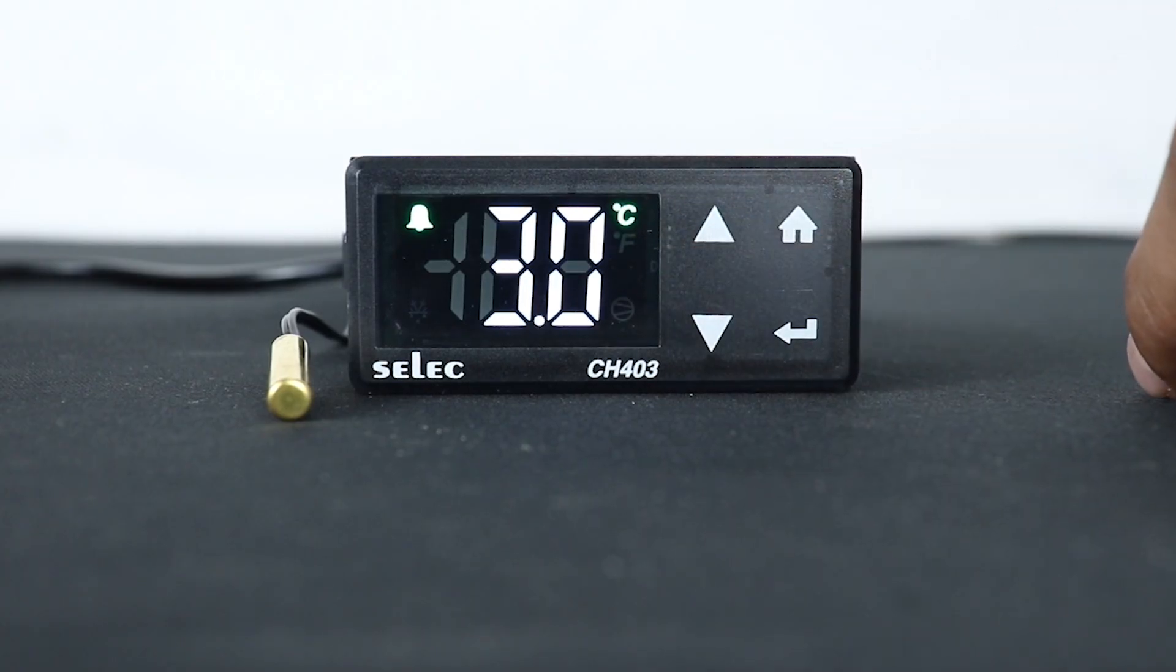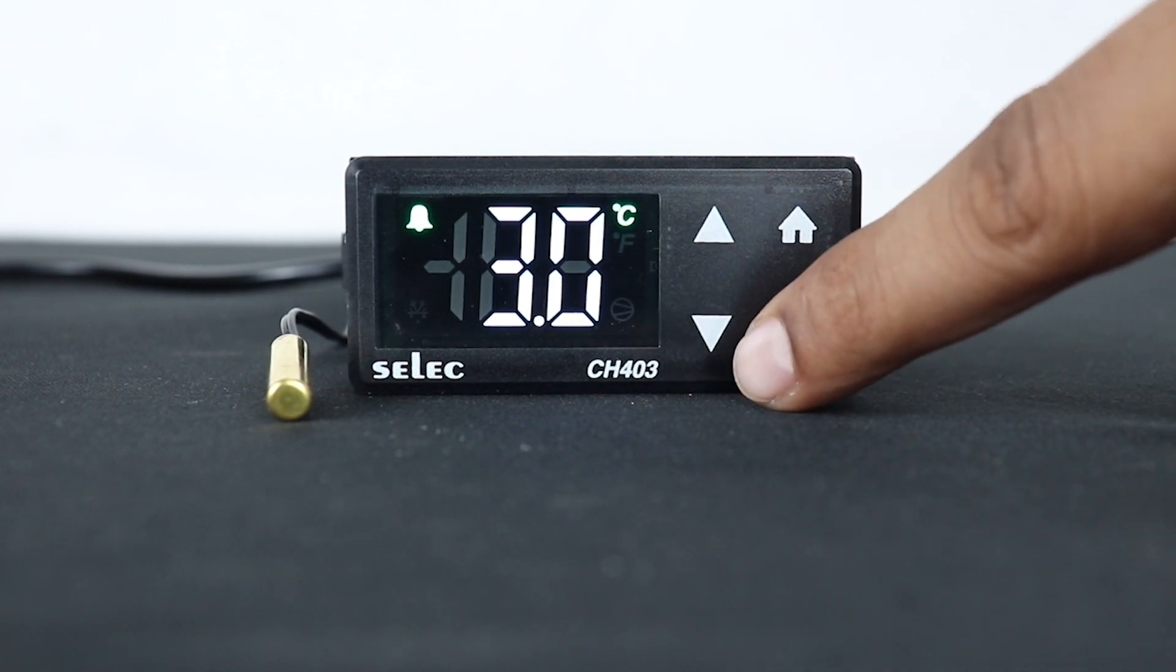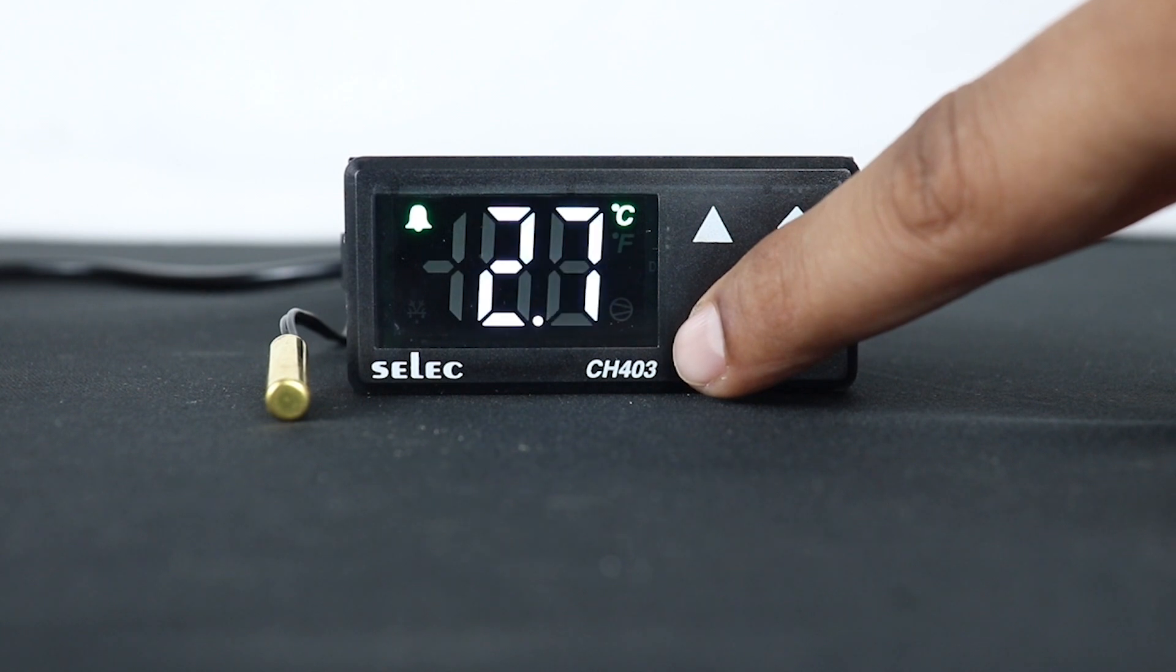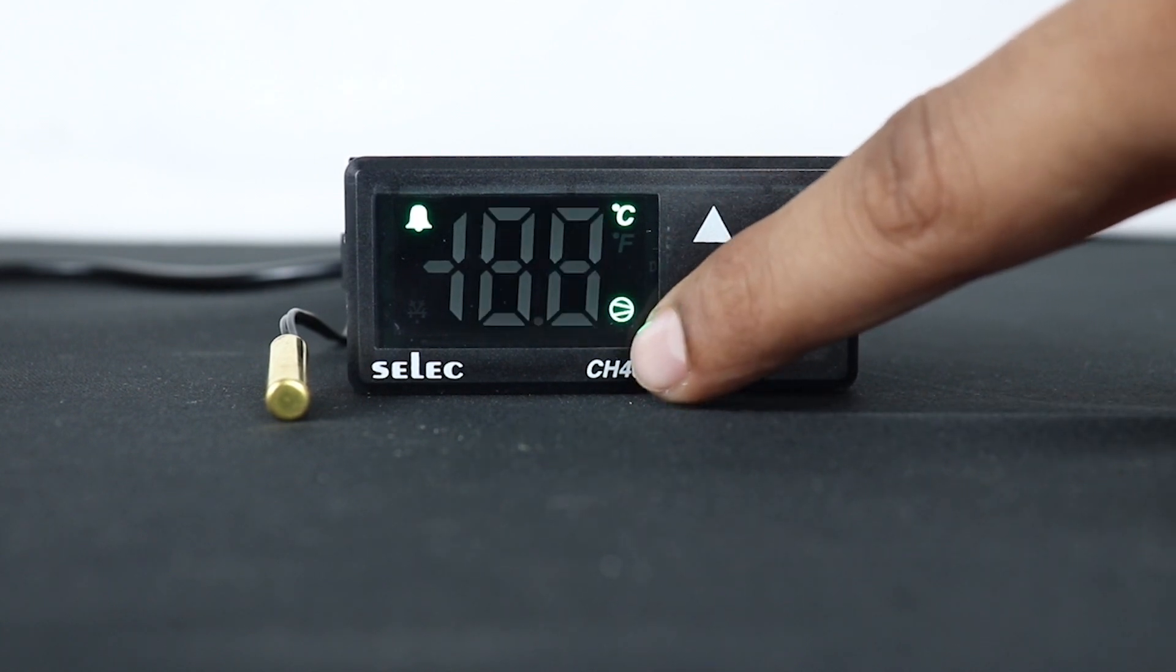P6 denotes restart time delay. By setting this parameter, user can set time duration after which the relay turns on after restart. It is used to prevent compressor from restarting in a short period of time.